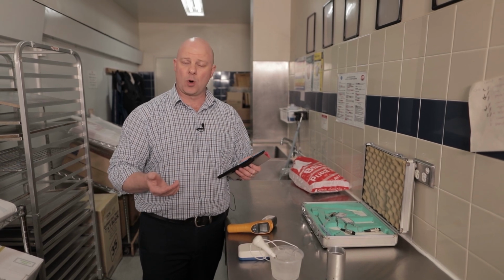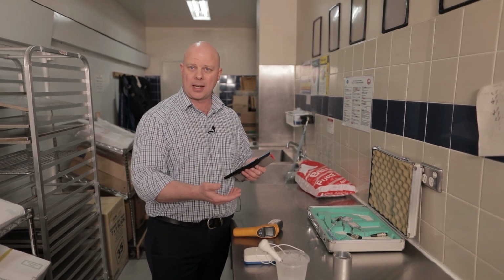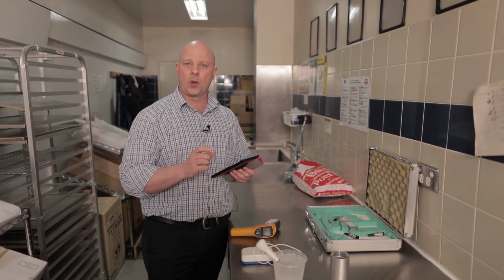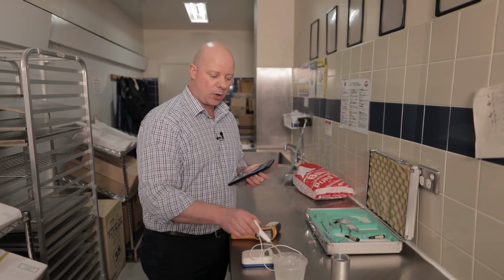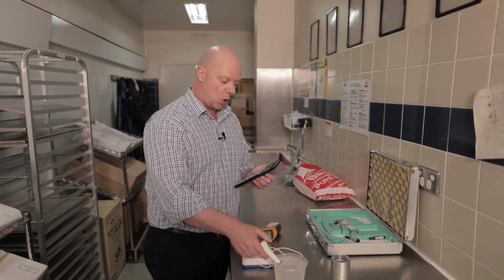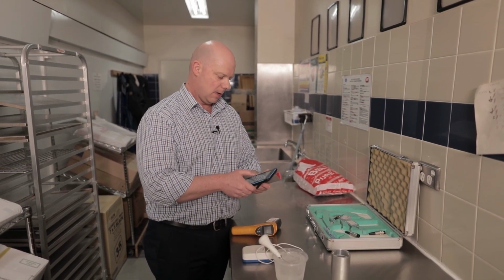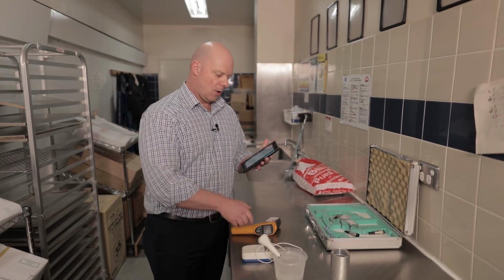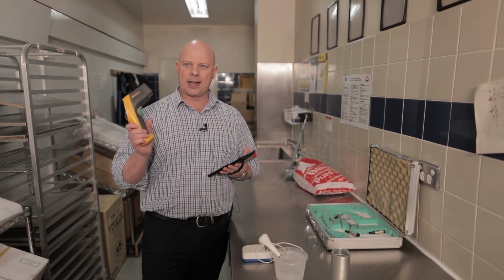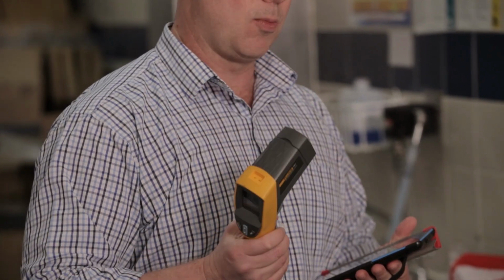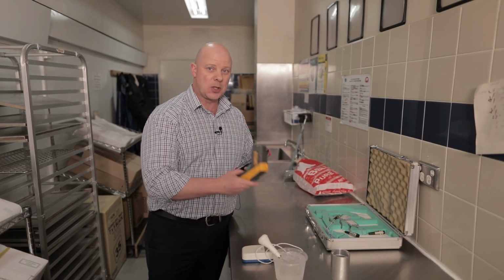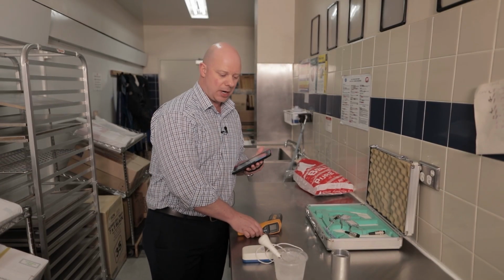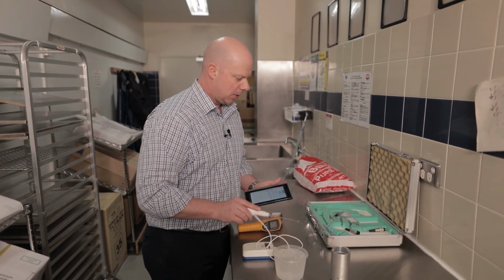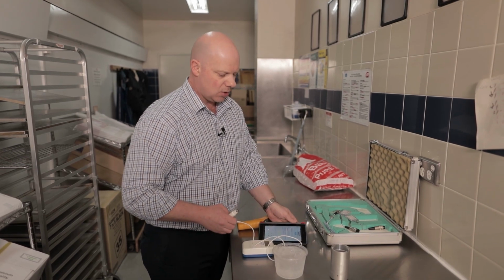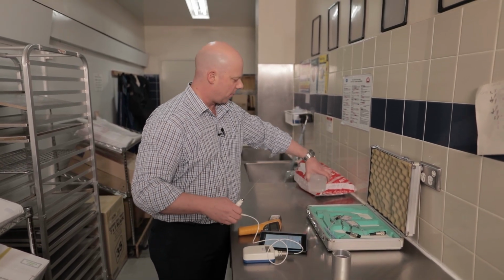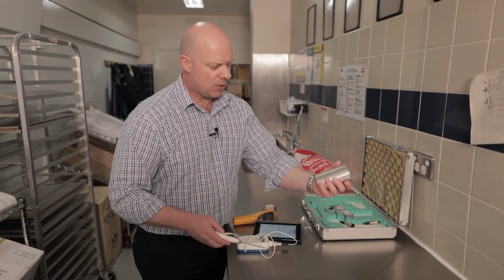Again, if you're doing a boiling water test, you would need to do that test again. You would need to boil your water, make sure that it's within plus or minus 1 degree of 100 degrees with your probe while it's on the boil. And then what we do, we want to make sure that our IR gun is accurate to plus or minus 1 degree of our probe. It's the only way you can do your calibration reading with your gun. So what we do is we use our comparator pot. Let's move that out the way for now. We use our comparator pot.